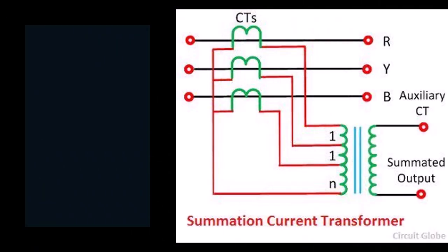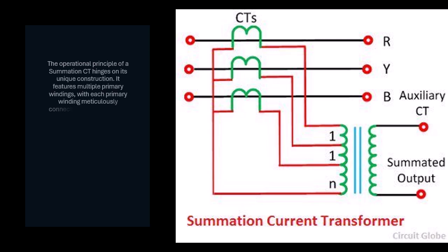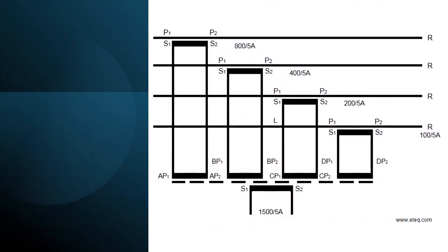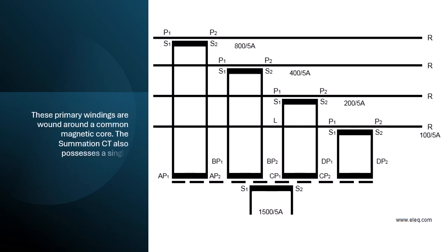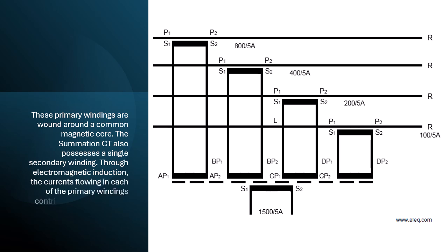The operational principle of a summation CT hinges on its unique construction. It features multiple primary windings, with each primary winding meticulously connected to the secondary output of a dedicated main CT monitoring a specific circuit or phase. These primary windings are wound around a common magnetic core.